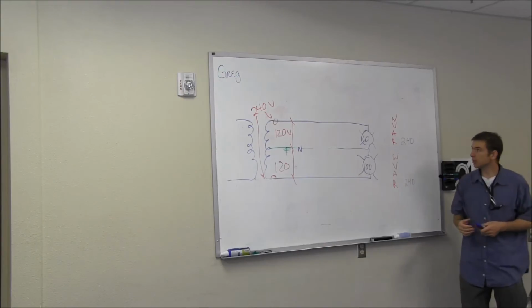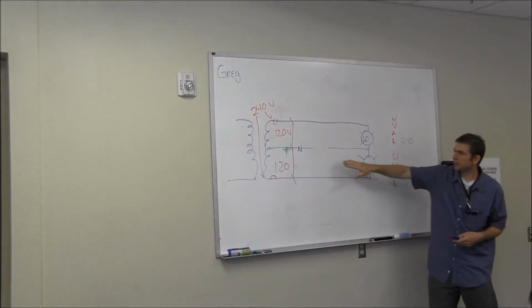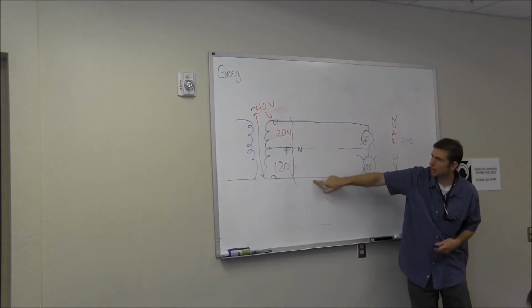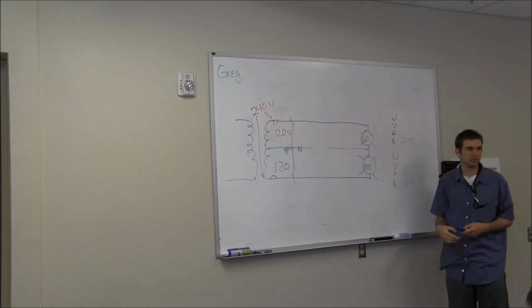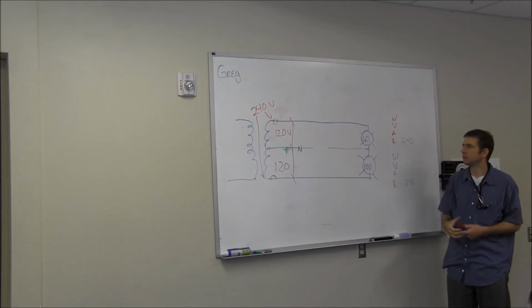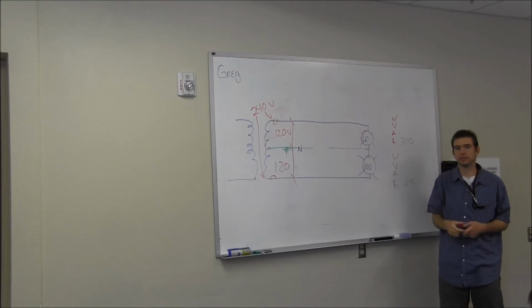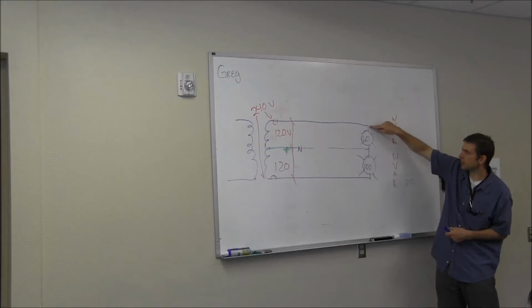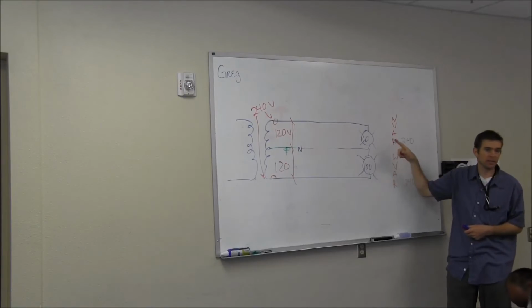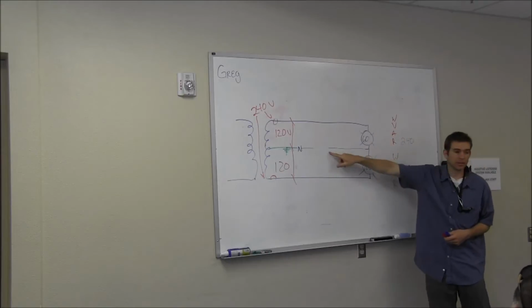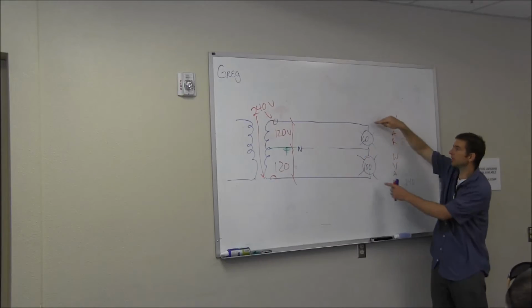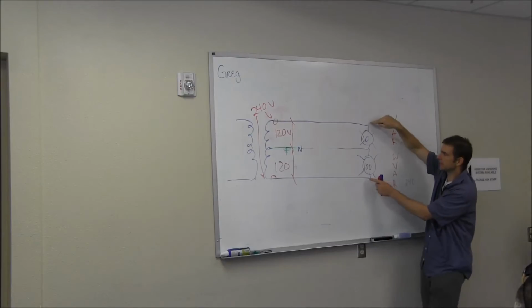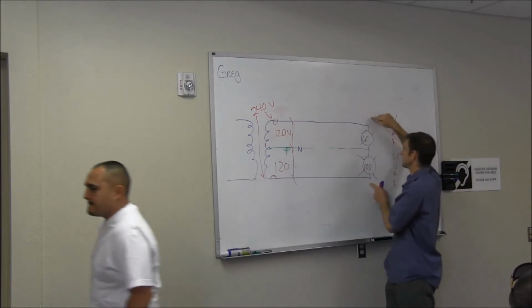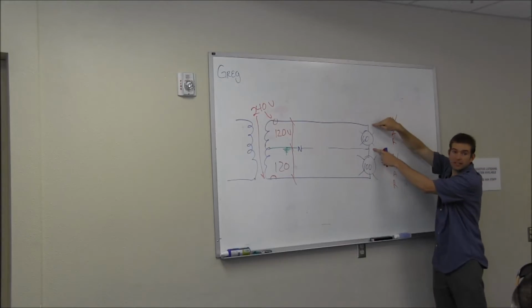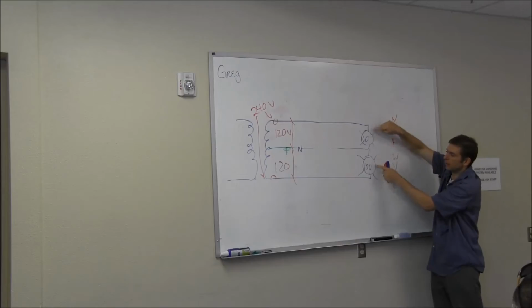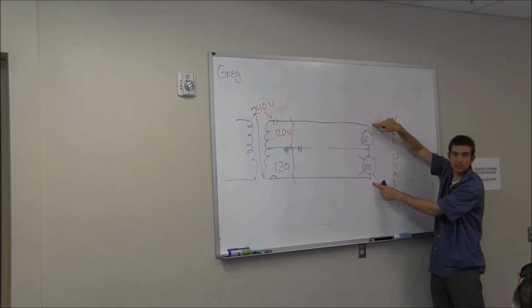Let's find out. So what do we know now? We've opened up our neutral. We have 240 volts from this wire to this wire. What is our circuit here? It's a series circuit. We had 120 here, now what do we have? 240. We have 240 volts from this to this. Just like when we talked about series circuits, we've lost 120 volts. We no longer have 120 volts, we only have 240 volts. If I take my tester and test it anywhere along this line, it's going to be 240 volts. If I test it here, it's going to be different, remember? Because we're going to lose voltage drop here, or voltage drop here. But if I test from here to here, it's 240 volts.